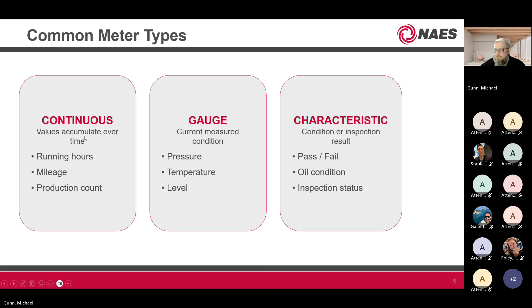There are different records that meters can be attached to. My recommendation is always to get it to the asset itself. Sometimes I've seen people put a meter on a boiler feed water overall location for pump run hours. That meter should be associated with that pump so we can pull up the pump and see all meters associated with it, giving an analysis over time, such as when outlet pressure starts dropping off.